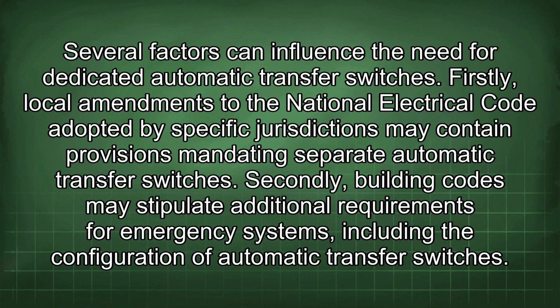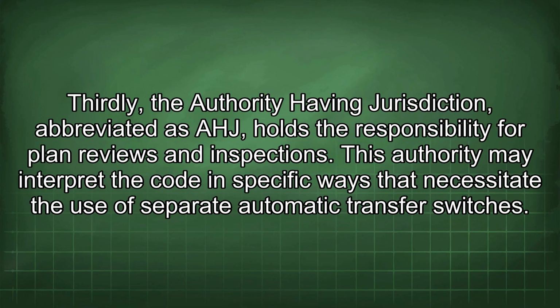Several factors can influence the need for dedicated automatic transfer switches. Firstly, local amendments to the National Electrical Code adopted by specific jurisdictions may contain provisions mandating separate automatic transfer switches. Secondly, building codes may stipulate additional requirements for emergency systems, including the configuration of automatic transfer switches. Thirdly, the authority having jurisdiction, abbreviated as AHJ, holds the responsibility for plan reviews and inspections. This authority may interpret the code in specific ways that necessitate the use of separate automatic transfer switches.